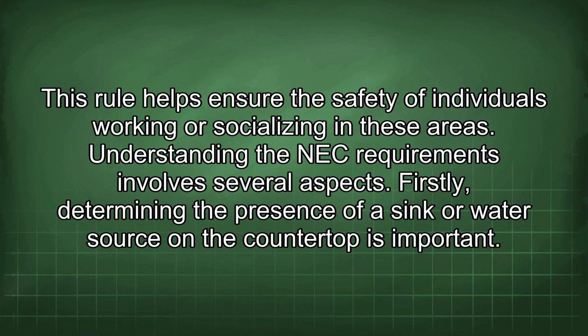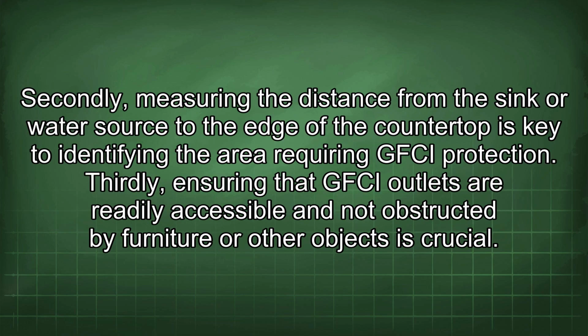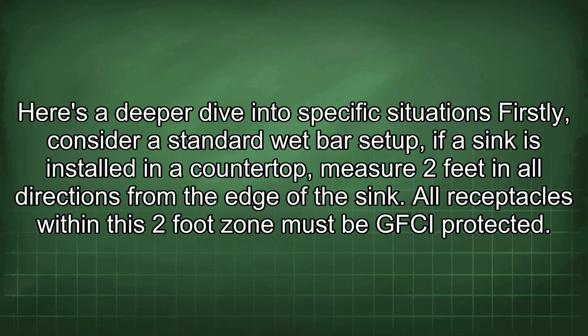Understanding the NEC requirements involves several aspects. Firstly, determining the presence of a sink or water source on the countertop is important. Secondly, measuring the distance from the sink or water source to the edge of the countertop is key to identifying the area requiring GFCI protection. Thirdly, ensuring that GFCI outlets are readily accessible and not obstructed by furniture or other objects is crucial. Here's a deeper dive into specific situations.